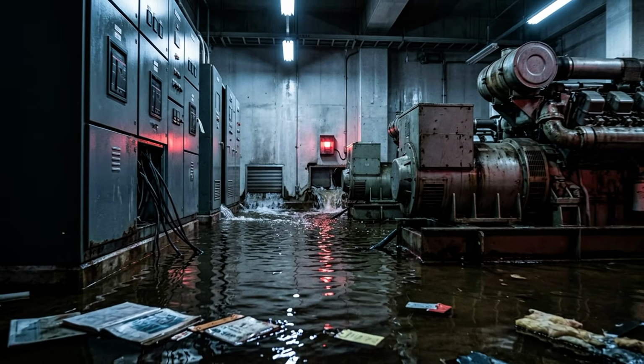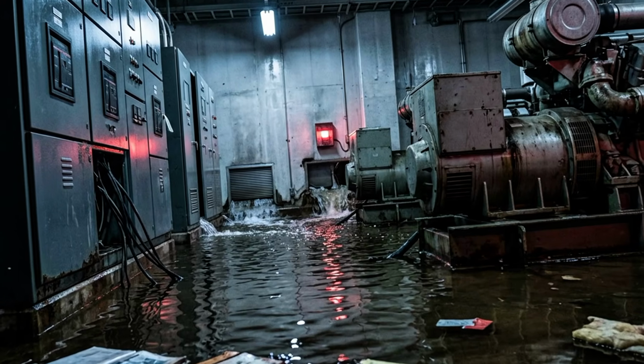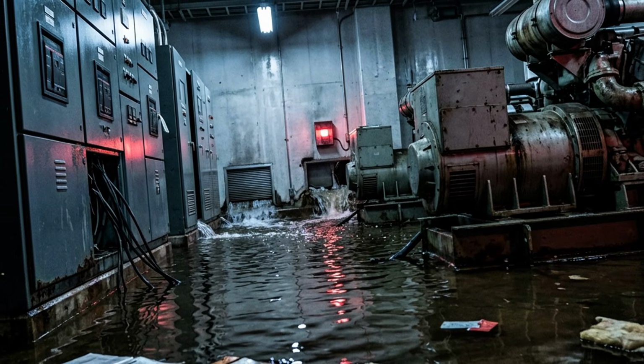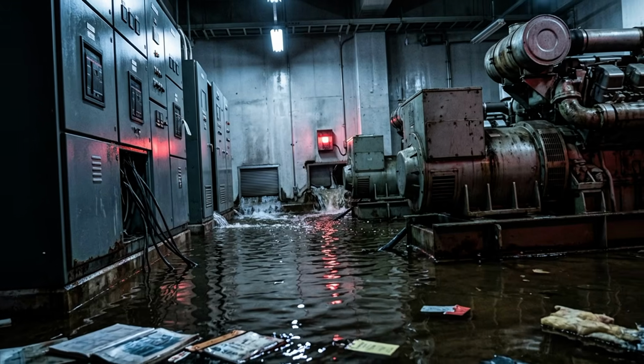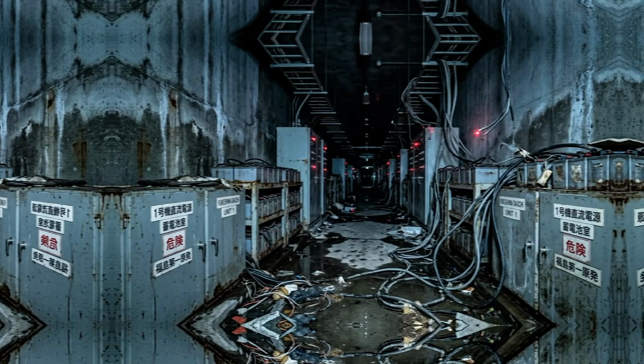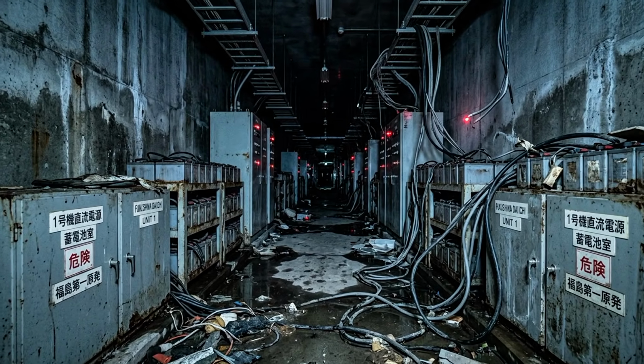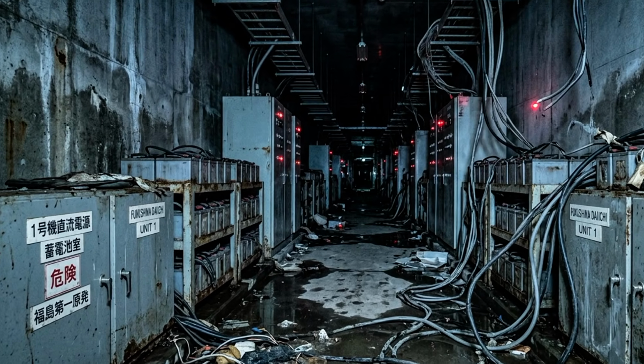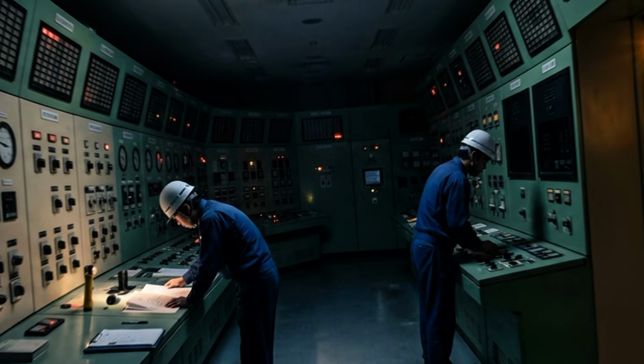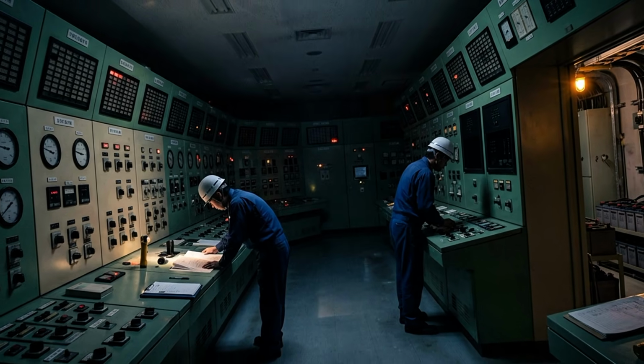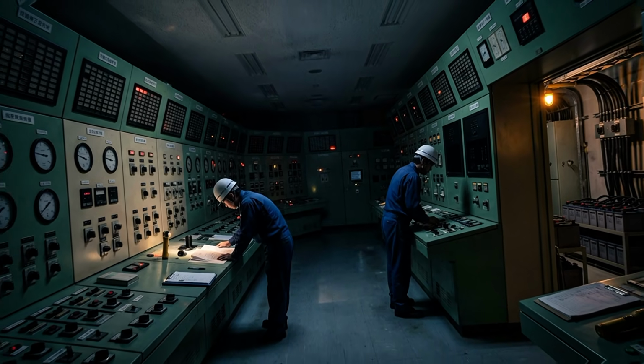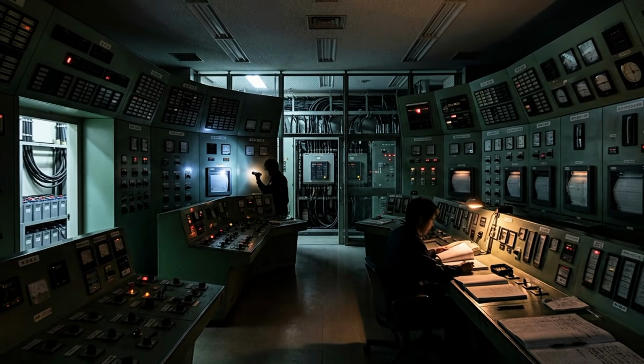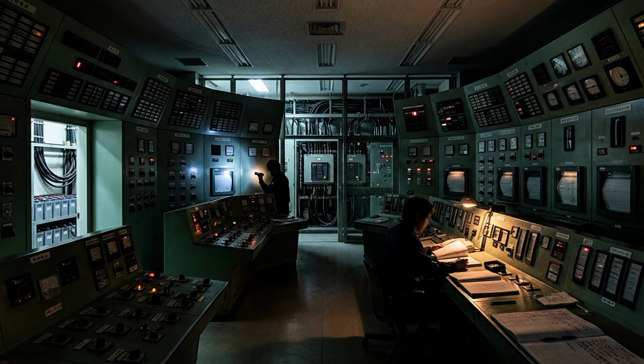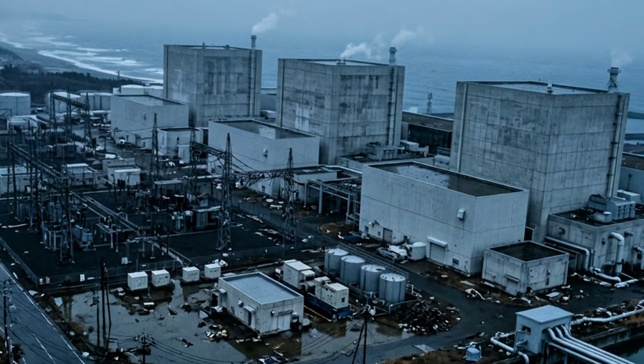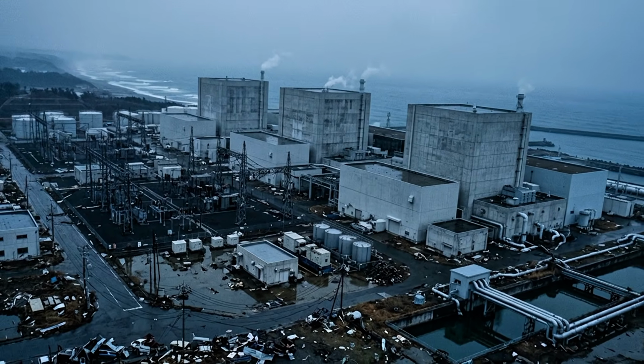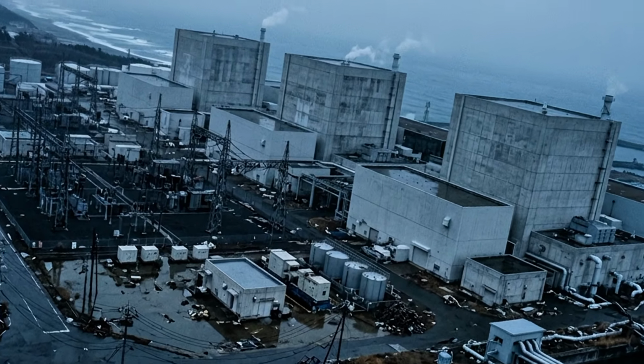Then the real wave arrived. Water reached critical electrical equipment. Emergency diesel generators were flooded or rendered unusable. Switchgear was damaged. Many batteries and electrical distribution systems were also lost or became unavailable. This was not simply a generator failure. AC power was disappearing. DC power was disappearing. Instrumentation and control capability were being degraded. The tsunami had attacked several functions that different safety systems depended upon. The reactors were still shut down, but the infrastructure required to keep removing their remaining heat was disappearing.